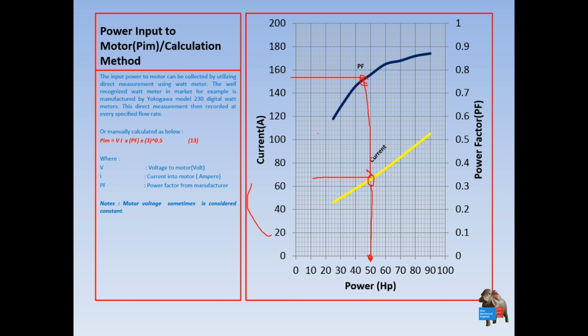From this you need to understand the power input to the motor, which you record, while the power output of the motor you measure with the power meter and so on. But sometimes you need to see the motor's own performance at specific currents, how much power is generated and what the power factor of this system is. So this is the manual calculation of the power input to the motor. You have voltage, you have ampere, you have power factor, and you have square root three, and then this will be the power input to the motor.